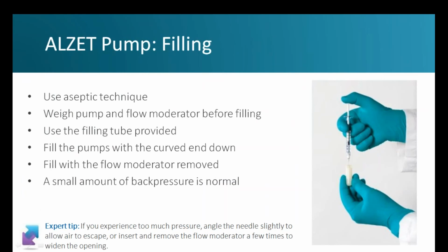The pump filling procedure is very simple and very straightforward. It is essential to use a sterile technique when filling the pump to avoid microbial contamination and infection after implantation. It is also important to use the blunt end filling tube that is provided with the pump. If using a bevel needle, that can puncture and damage the reservoir. When filling the pump, a small amount of back pressure can be expected, and this back pressure can be more pronounced when filling with viscous solutions. So it is recommended to fill the pump slowly to avoid the formation of air pockets during filling. After filling, the flow moderator is inserted into the pump through the existing orifice.